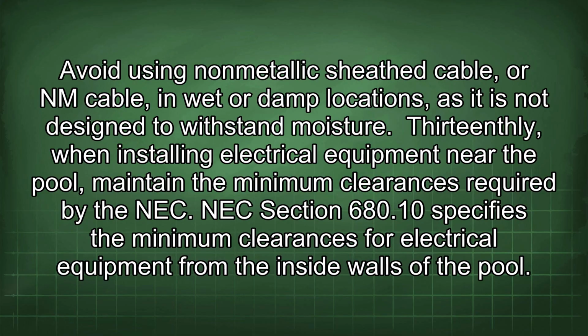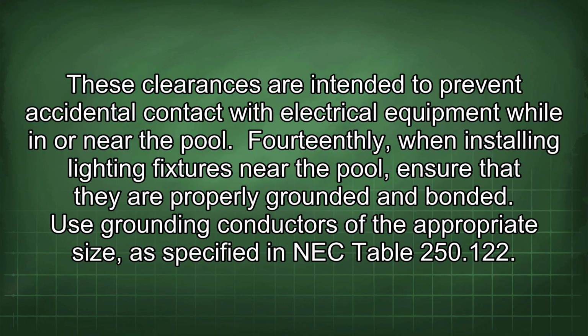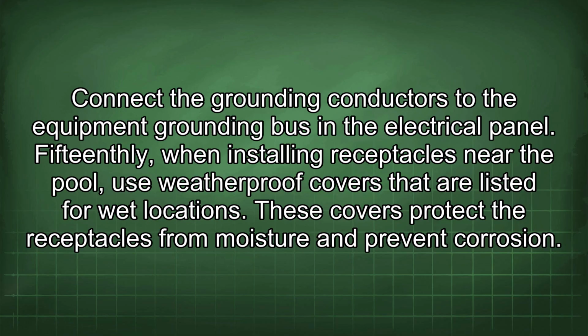13thly, when installing electrical equipment near the pool, maintain the minimum clearances required by the NEC. NEC Section 680.10 specifies the minimum clearances for electrical equipment from the inside walls of the pool. These clearances are intended to prevent accidental contact with electrical equipment while in or near the pool. 14thly, when installing lighting fixtures near the pool, ensure that they are properly grounded and bonded. Use grounding conductors of the appropriate size, as specified in NEC Table 250.122. Connect the grounding conductors to the equipment grounding bus in the electrical panel.